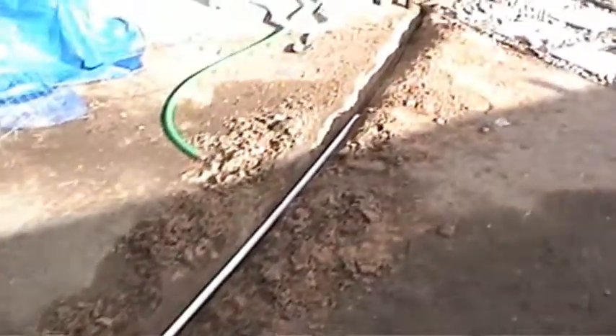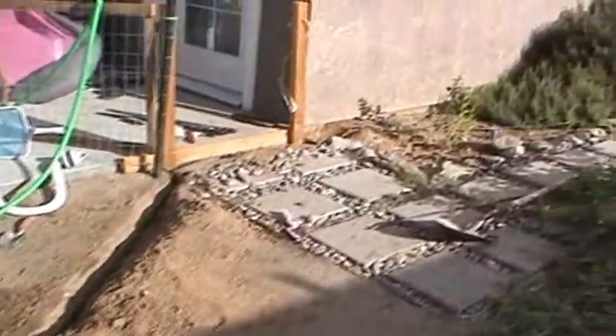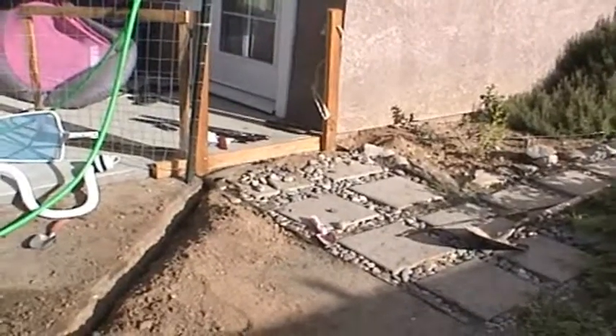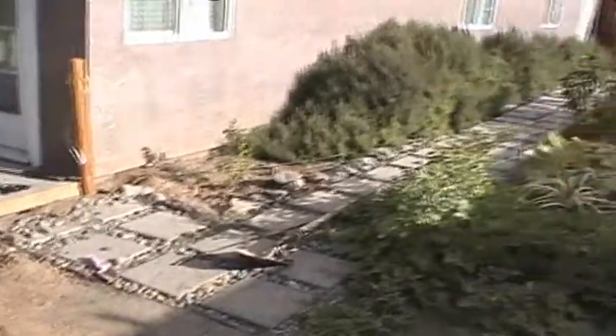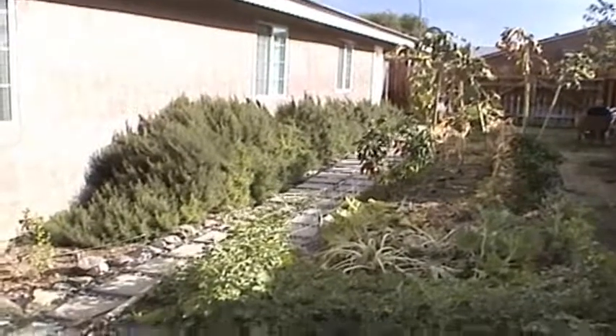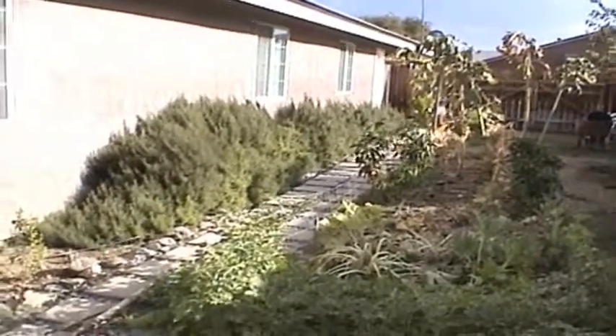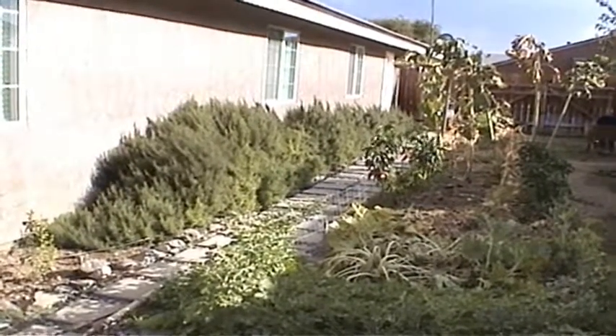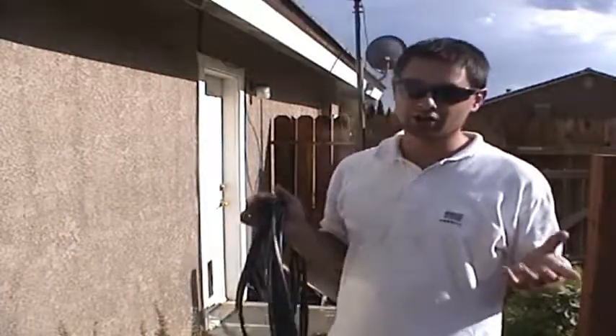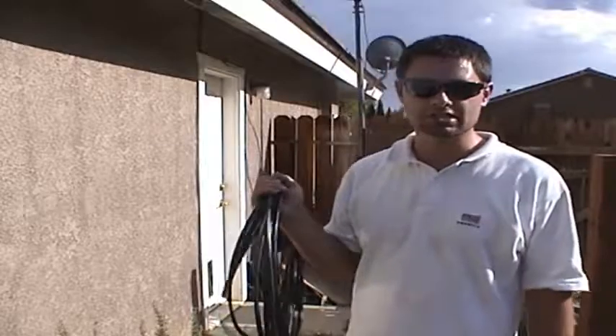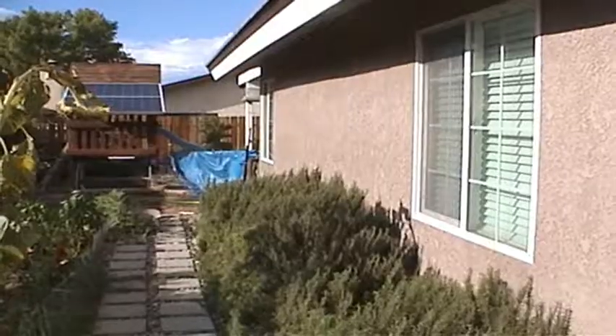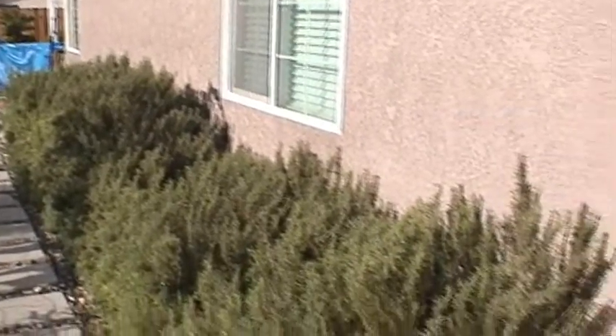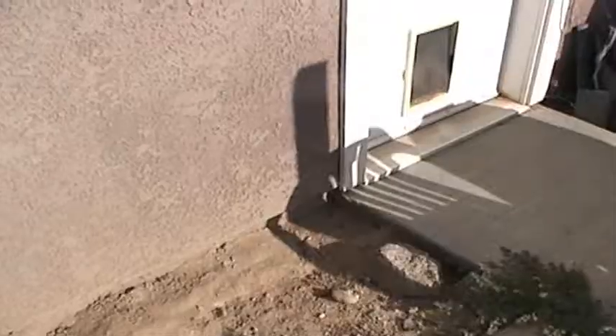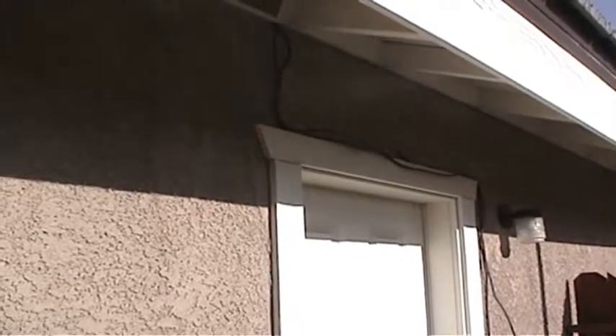Okay, we're done running the outdoor cable through the PVC. Now remember, your yard, your layout is going to be different than mine. And so you're going to have to be creative in the way that you run your outdoor cable. But there are some important things to remember. Even though this cable is outdoor cable, it will last a lot longer if you keep it from being exposed to sunlight all the time. I'm going to run it next to my house behind these bushes. And then up this wall, through a hole into my attic and down to my battery bank.